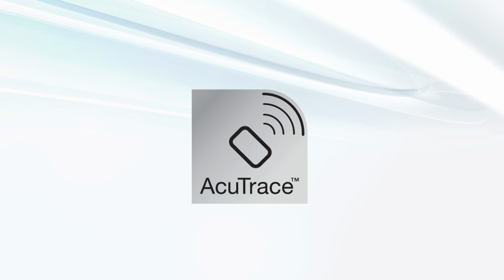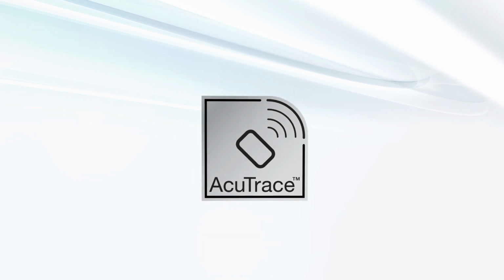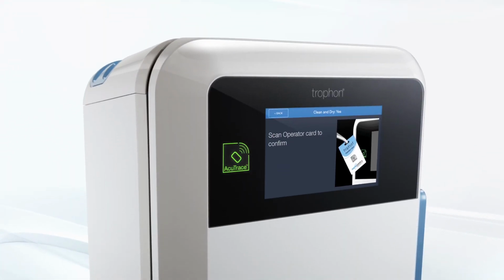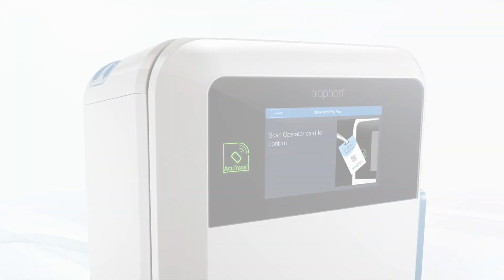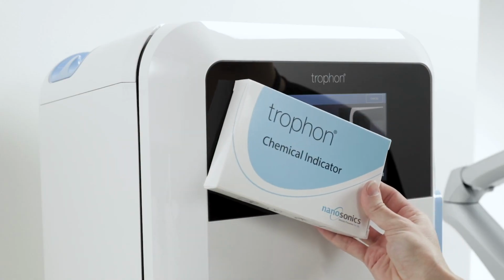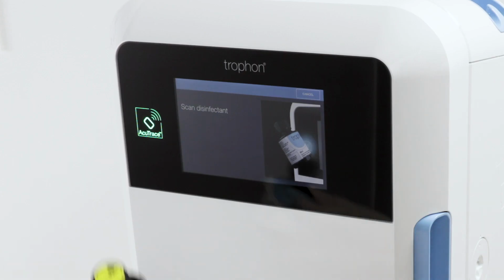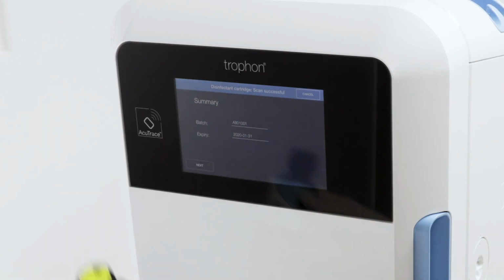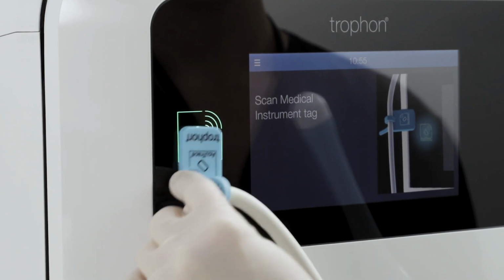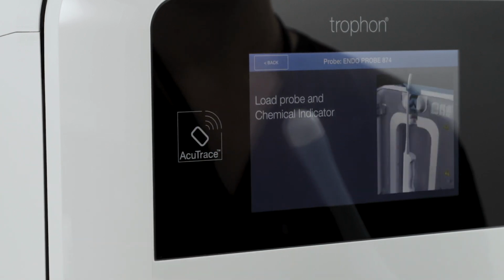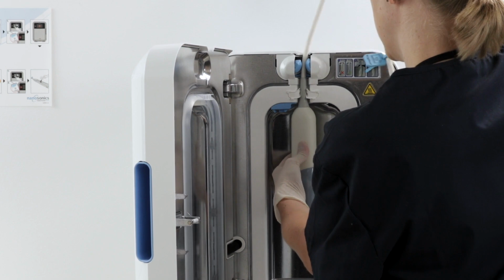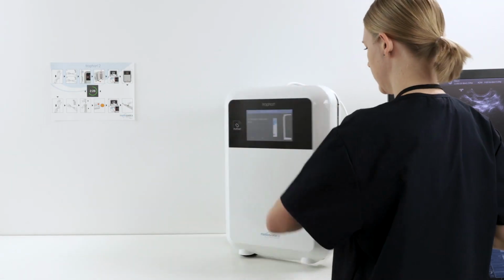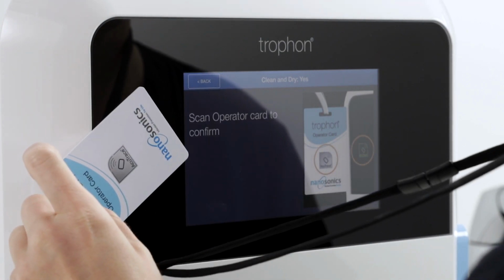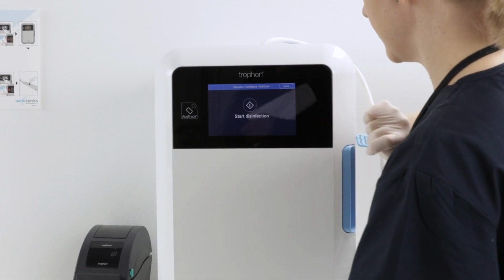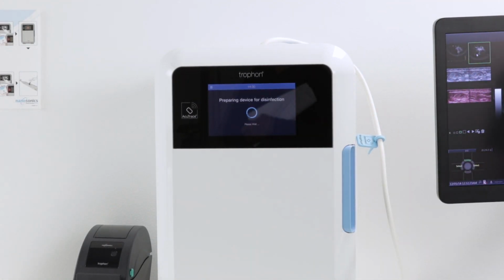AcuTrace is an automated HLD traceability system that uses RFID, radio frequency identification technology. trophon2's AcuTrace-enabled accessories and consumables contain RFID chips that store digital information. As you step through the ultrasound probe reprocessing workflow, the built-in AcuTrace reader captures and stores the digital data. AcuTrace simplifies the creation of accurate, audit-ready digital disinfection records and stores over 100,000 records directly on your trophon2.